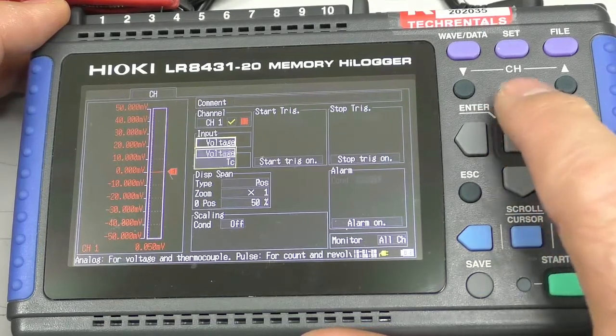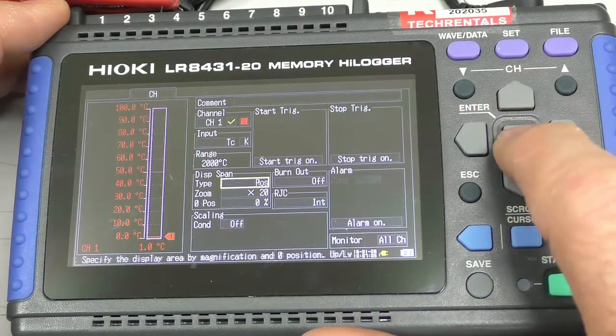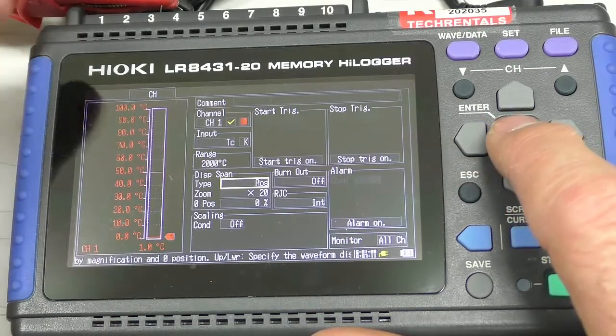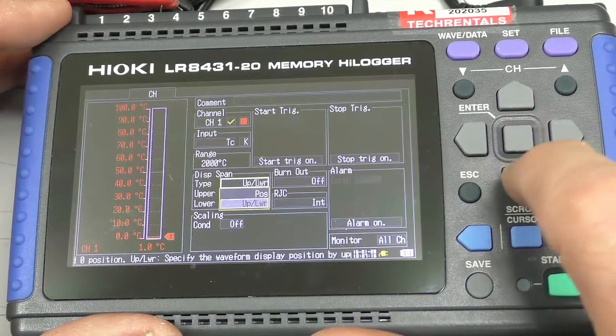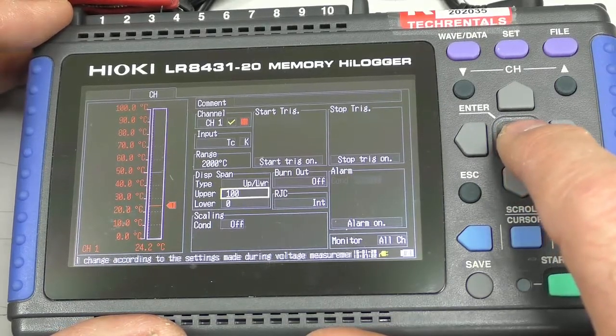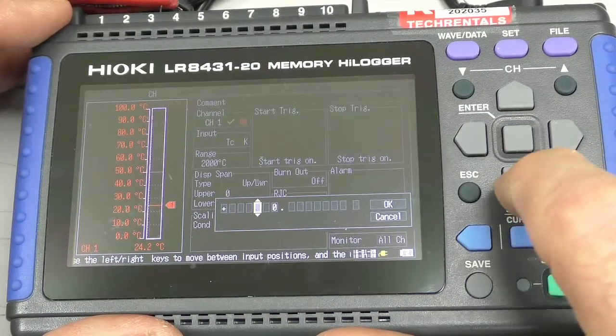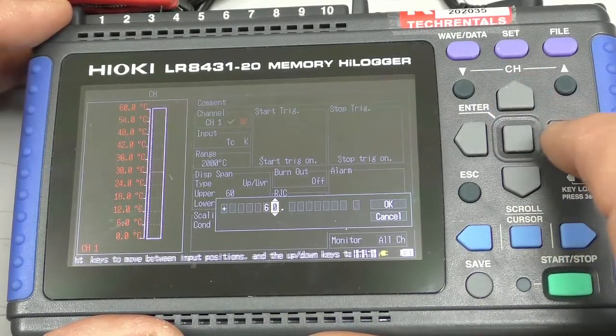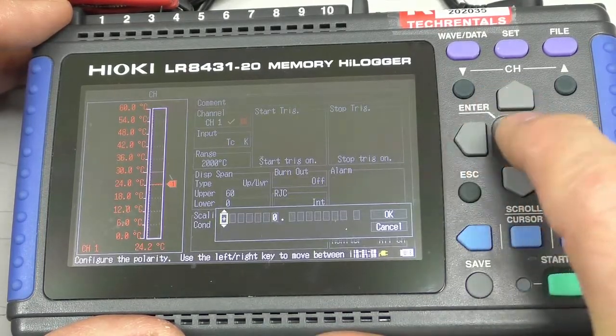At the moment the input is set to Voltage. I'll come down here and set it to Type K thermocouple. That's a standard range of 2000, but I want to display a default. You can set it, say, 0 to 100 degrees. Let's pretend we wanted some other range — I'm going to set an upper and lower. So the upper value: let's make it between minus 40 and 60. I'm going to set the upper range to 60.